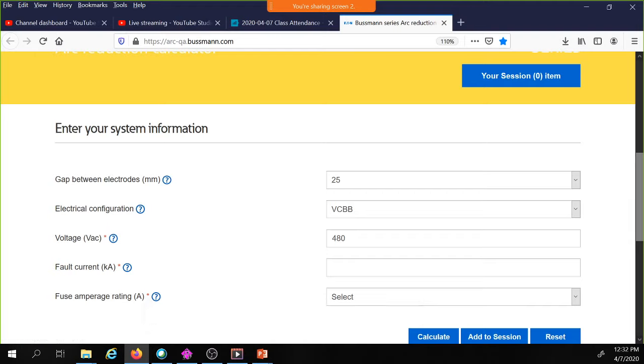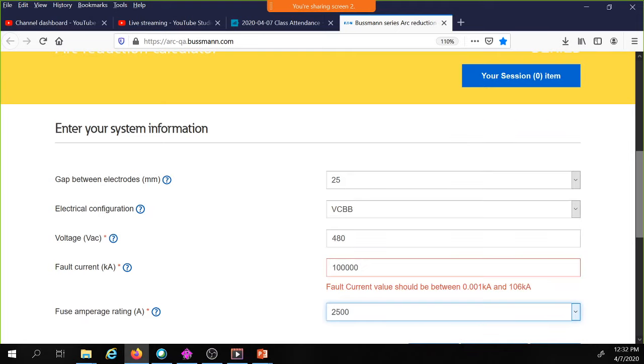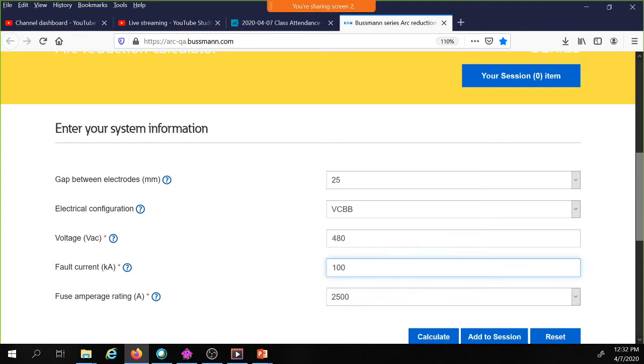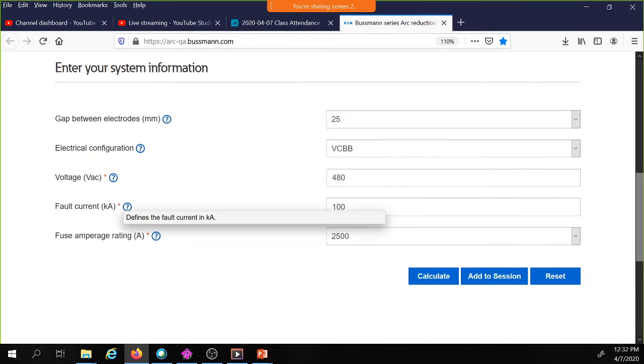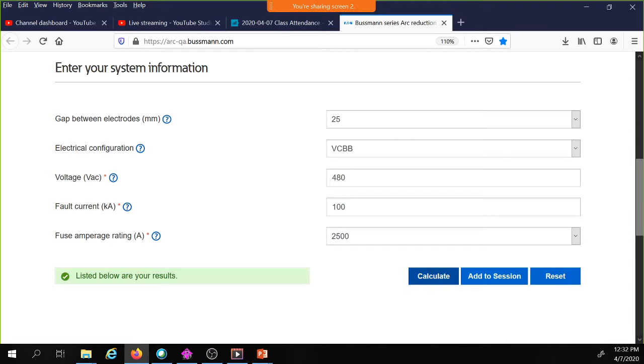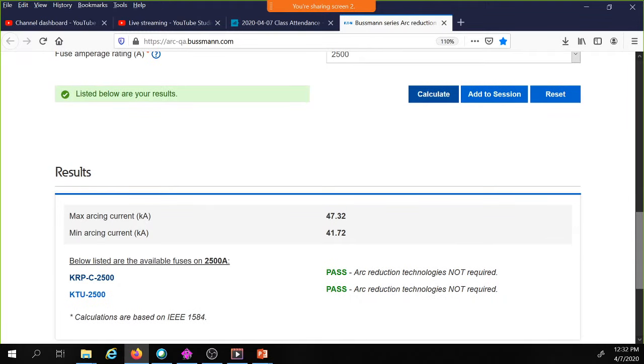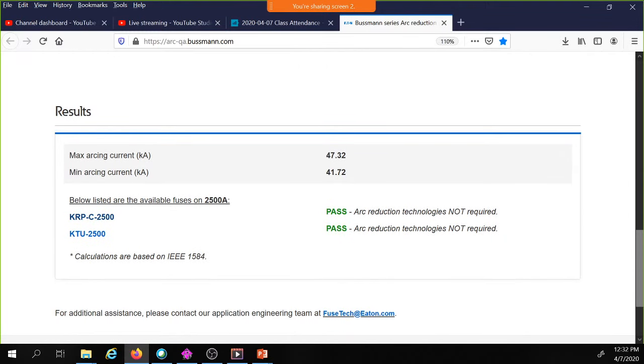So if I have these gaps, 480 volt system, and let's say I have a 2500 amp fuse. Actually, that's the fault current. Let's say I have, I don't know, 100,000 amps of fault current, and I'm going to pick a 2500 amp fuse. It's all in kA, so you see, you're learning as I am. So 100 kA, 2500 amp fuse. I calculate. We have little scientists back at the lab who do these calculations for us. And we have the maximum arcing current is 47.32, and we have a minimum arcing current.